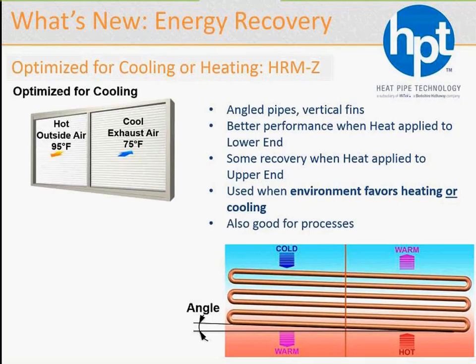This is optimized for heating. Which is optimized for heating, for cooling, I apologize. Cooling or heating, HRMZ is used for both. This particular one we're showing is optimized for cooling. How do I know? The 95-degree outside air is to the left, and the cool exhaust air is to the right, at 75 degrees. This is doable with a little angle, a little slope that we apply to the tube length.